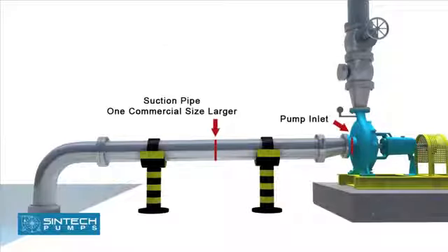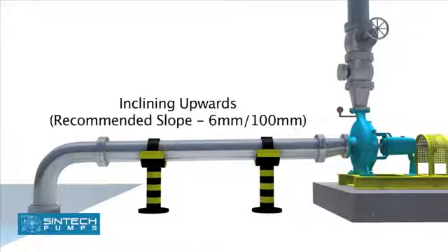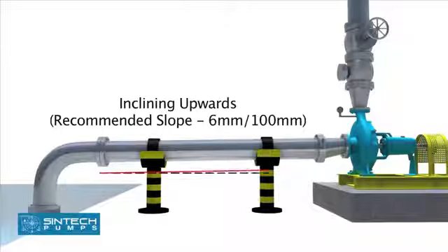The suction pipe size should be at least one commercial size larger than the opening of the pump inlet. All suction pipes should have a continuous rise to the pump suction inlet. 6mm per 100mm slope is recommended.